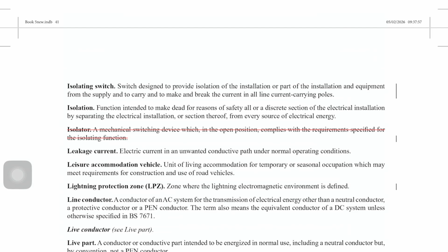Okay, so you can use the words, which device are you using for isolation, but the term isolator should be removed from the book altogether. So it's something colloquial, a bit like the earth wire thing with the CPC. So you say, oh, where's the isolator? Right, it should be, where's the switch disconnector? So it's just got to get used to the new terminology.